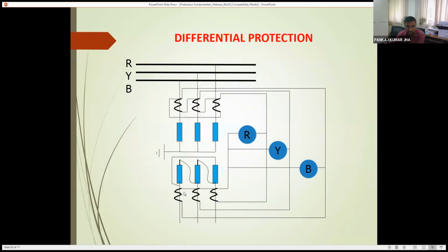So now, how does this differential protection work? Basically, you can have two different types of differential protection. It can be the high impedance type, or it can be the low impedance type. For a low impedance type, I have connected the HV side CT, IV side CT or LV side CT, whatever it may be, to the relays, and now the relay will calculate the differential and stabilization current based upon the current magnitude from the HV and LV side, and simple Kirchhoff's law will follow.